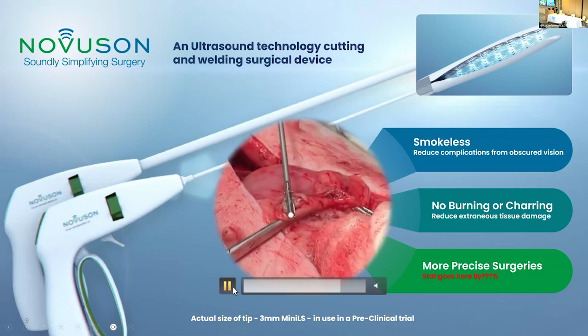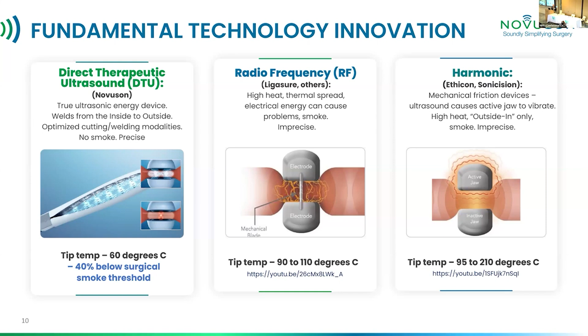What differentiates Novuson's technology from other technologies is we use direct therapeutic ultrasound to weld the tissue together, and we use ultrasound to cut the tissue. Ultrasound is more efficient than radio frequency, which is in the center screen here, where they pass electricity through the tissue to cauterize it and a mechanical knife to cut it, or the harmonic devices, which basically use mechanical friction to burn through the tissue.